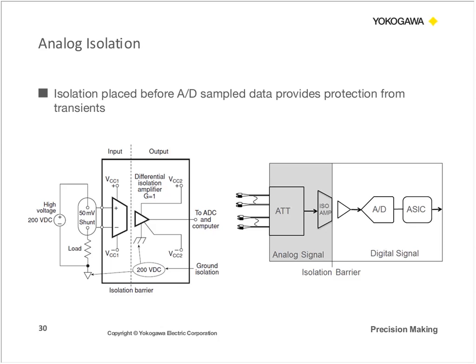And what you're doing essentially is creating an isolation barrier. So your input signal goes into the attenuator that may amplify or change the gain of the signal, and that signal will be passed on to the isolation amplifier. At that point, you have an isolation barrier that protects the A to D converter as well as the ASIC in your data acquisition. So you're going to protect your system, and it's also going to allow you to, again, measure the small signal changes in the presence of high common mode voltage. For example, we talked about earlier in the example on the left, you're trying to measure the 50 millivolt change in the presence of 200 volt DC common mode voltage.